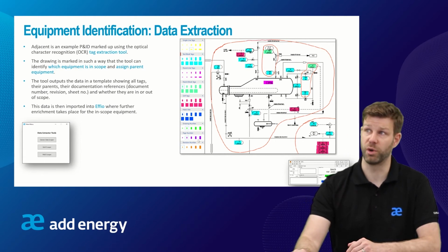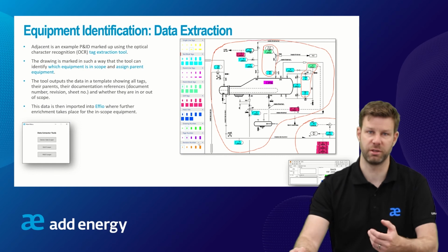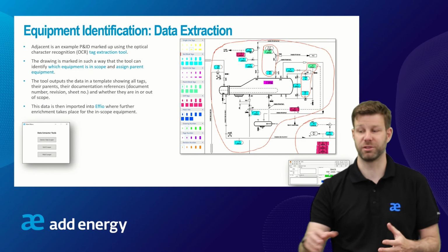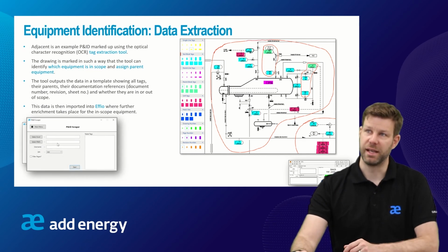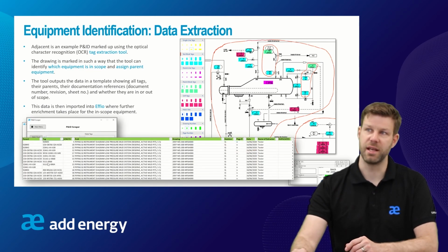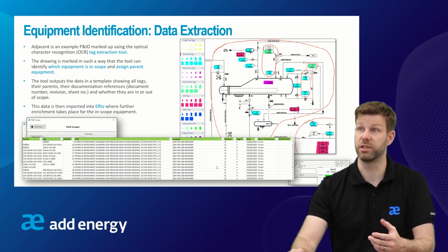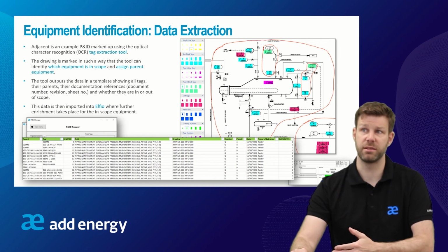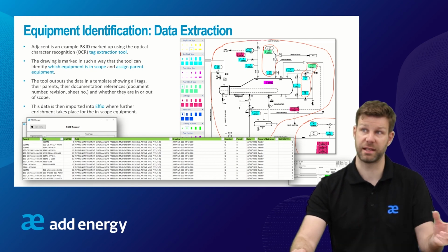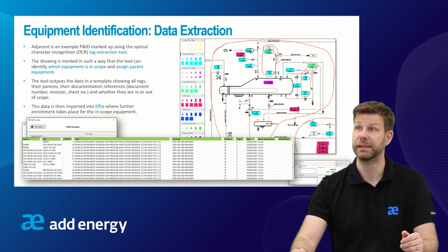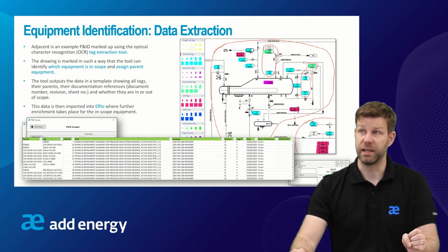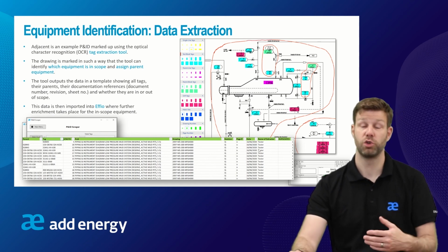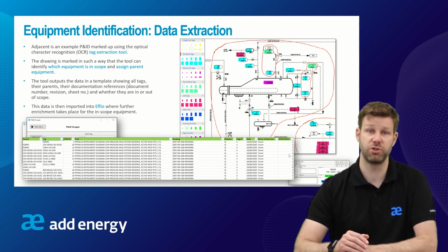So what you've got also is the drawing numbers, P&ID titles, page numbers, revision numbers, all the sort of things that would be in the bottom right hand corner of your P&ID, which is critical information. So what we want is to have an extracted CSV file or Excel file that you can read in there that would then align with that marked up P&ID, which gives you the parent, the tag, the length of the tag number as well, which is something that is particularly useful later on, the P&ID description, the drawing number, the revision, the page number, the date it was extracted, who extracted it, and also if there's any duplicated tags.